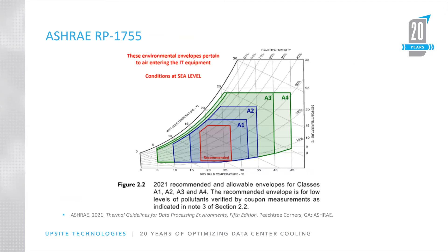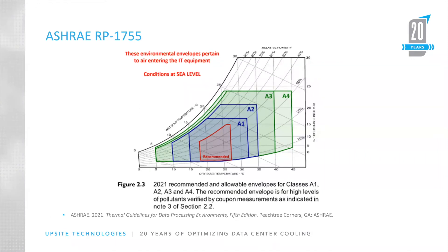Here is an excerpt from the updated thermal guidelines showing the scenario where corrosion rates are low. You can see that the upper relative humidity corner of the recommended range is now up at 70%. Compare that to the recommended range when you detect high levels of pollutants and therefore corrosion, and you can see that relative humidity has been lowered down to 50% — taking a pretty healthy chunk out of the cooler, damper area of the recommended range. That was really the primary outcome of Research Project 1755. The research itself was far from simple and extremely interesting, but this is the primary functional takeaway for the design and operation of your facility.